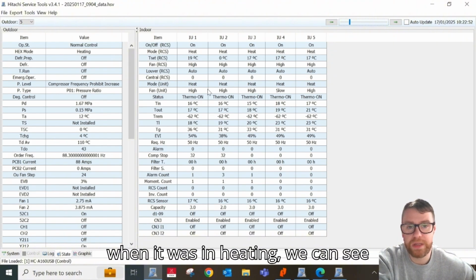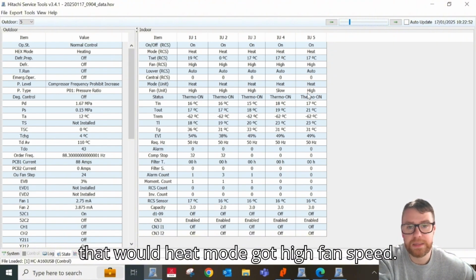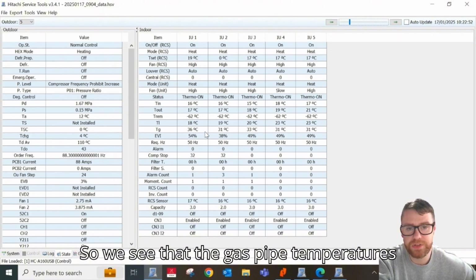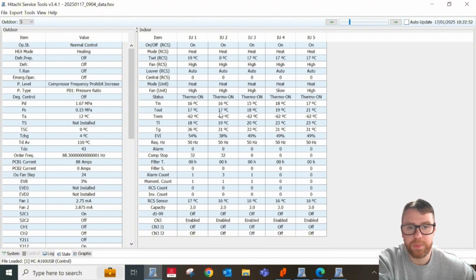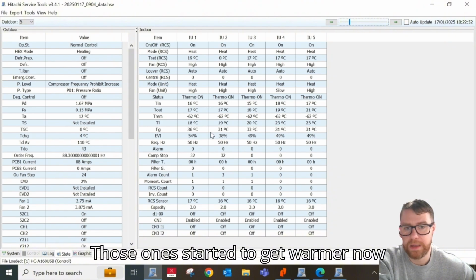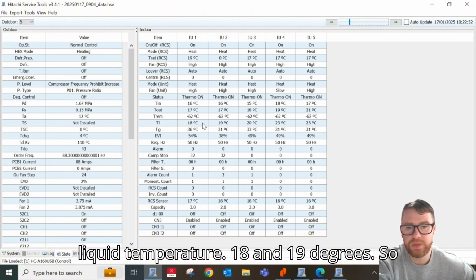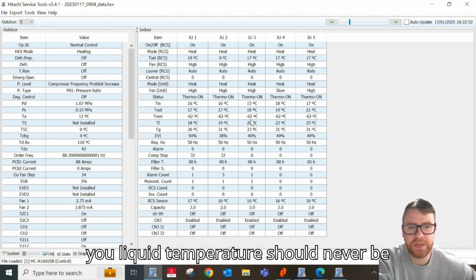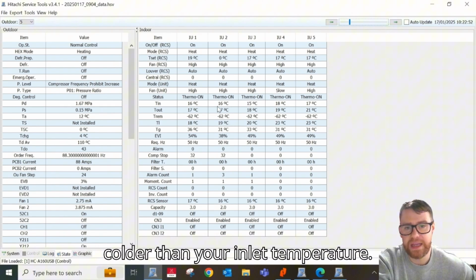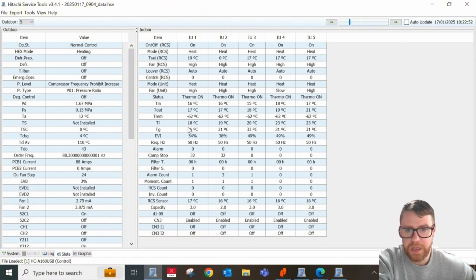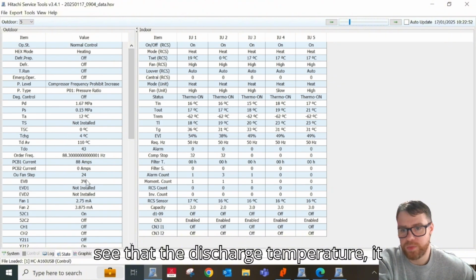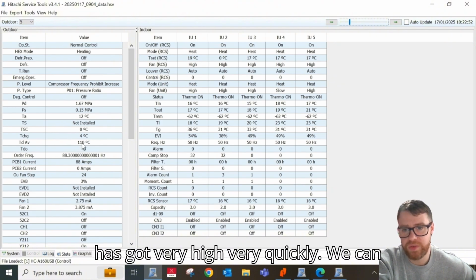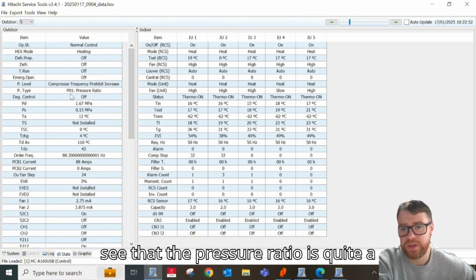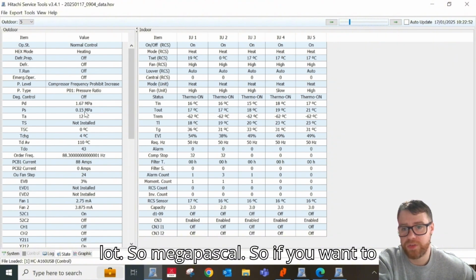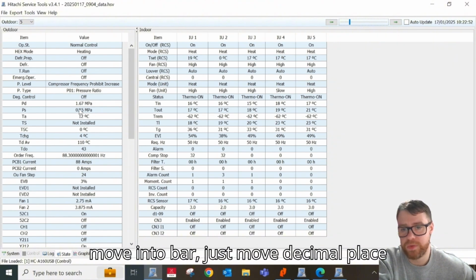we can see that we're in heat mode, got high fan speed, so we can see that the gas pipe temperature is starting to build up, so 36 degrees, 31 of those ones. Temperature is starting to get warmer. Now, liquid temperature between 18 and 19 degrees, so your liquid temperature should never be colder than your air inlet temperature. Now, on the outdoor information, we can see that the discharge temperature has got very high very quickly. We can see that the pressure ratio is quite a lot. So megapascals, if you want to move it into bar, just move the decimal place over.